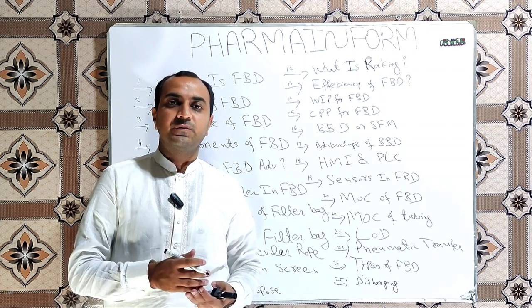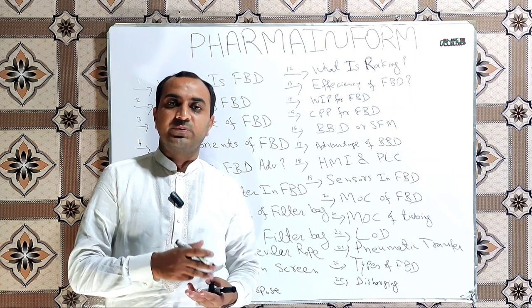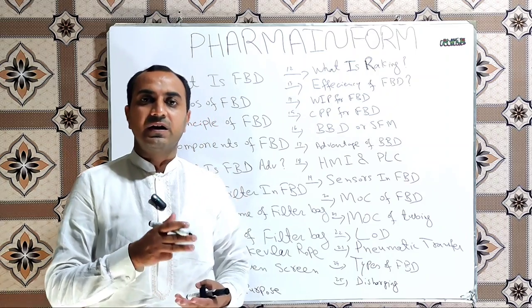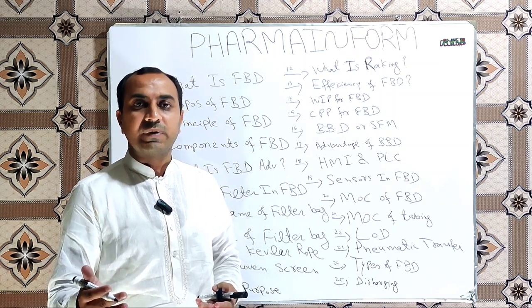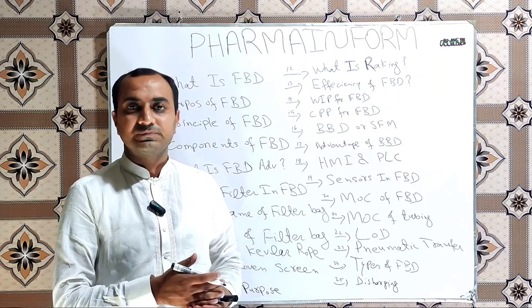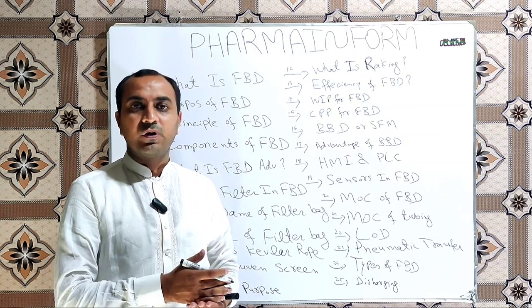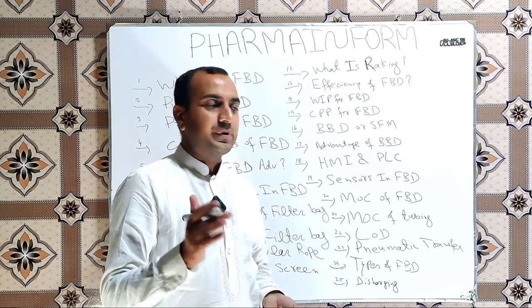So in brief, the most important parts of FBD are product trolley, expansion chamber, lower plenum, inlet duct, outlet filters, commonly bag filter or SS filter, some sensors, and sampling port are the most important components of fluidized bed dryer.